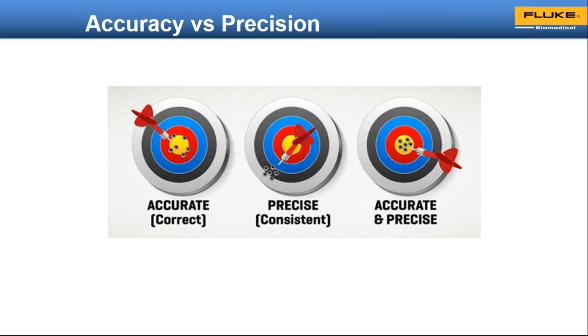And you can look on this slide and you can see the difference between accuracy, that is being a correct measurement, and precision, which is just being consistent in the grouping of measurements that you're making. So you can see that just being precise is not good enough because we could be off target, off the bullseye, whereas accuracy puts us in the bullseye. If we have both accuracy and precision, we are not only in the bullseye, but our grouping of measurements is much tighter, meaning there's much less variability, meaning we can be more certain that the measurement that we made is indeed the measurement that we expected.